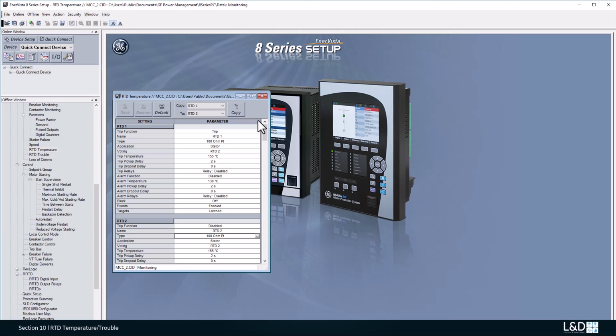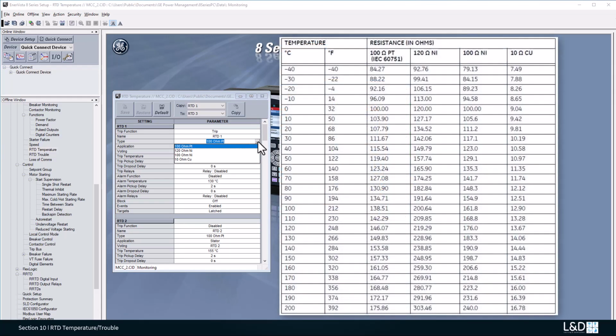Each RTD can be configured to have a trip temperature and an alarm temperature. The trip temperature is normally set at the insulation rating. The alarm temperature is normally set slightly above the normal running motor temperature. There are 4 types of RTDs: platinum, nickel, 120 ohms, and 100 ohms, and 10 ohms copper. The resistance of each type of RTD can be converted into different temperatures according to the conversion chart.